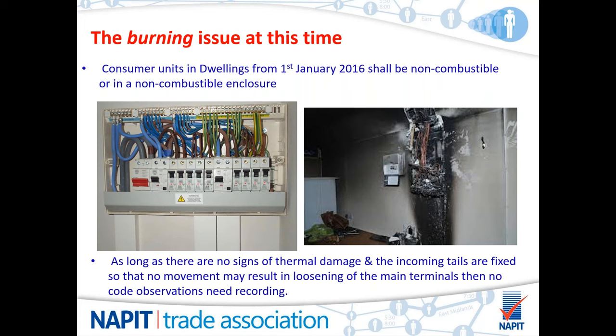Now, as you can see in the picture from the left-hand side, nice neat consumer unit, as you can see with the meter tails located in trunking, so they're nice and secure. So another possible way of determining whether this would need a code raising against it would be potentially the use of a thermal imaging camera, which would then show you any loose connections and so forth. As you can see from the picture on the right-hand side, no thermal imaging camera was used on this one. And as you can see, there was obviously an issue as it's gone up in flames. And I think that's all we need to say about that one, really.